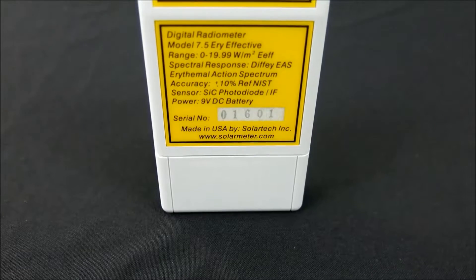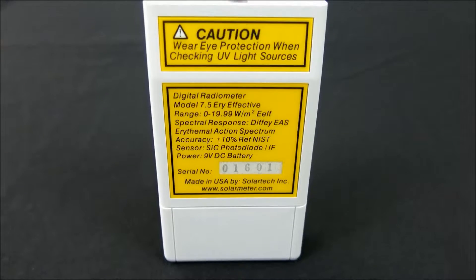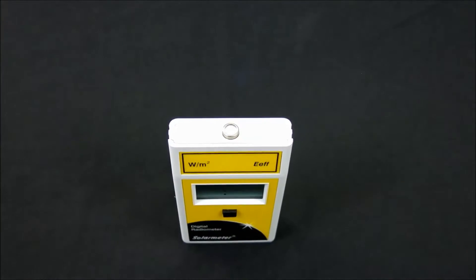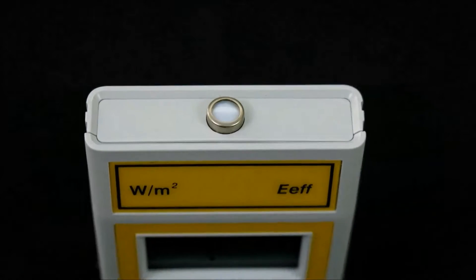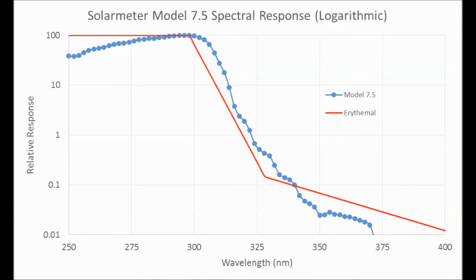Resolution is 0.01 watts per meter squared with extremely high accuracy of plus or minus 10%. The sensor and filter response closely follows the erythema action spectrum, which enables accurate readings from virtually any UV source. The sensor itself is a silicon carbide photodiode packaged in a hermetically sealed UV glass window cap with an interference filter to block UV above the erythema response, as shown on this graph.